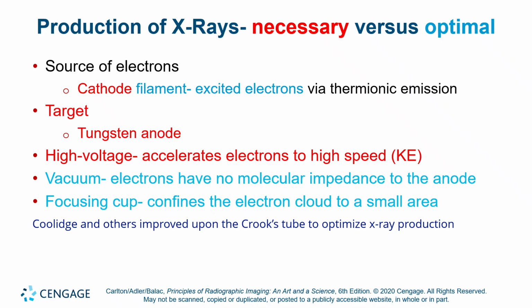Okay, so we need a source of electrons. We need a means to accelerate them. That's the high voltage supplied by the X-ray circuit and the high voltage transformer. And then we need a target for them to slam into. Now the atomic number of the target material determines the characteristic photon emissions that we get out of the target material. Tungsten has a characteristic emission of 69.5 keV, which is right in the middle of the diagnostic range, so that's very handy. We basically get bonus X-rays if we use tungsten as a target. That is one of the reasons we're using tungsten as a target material.